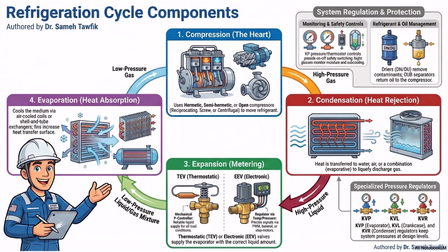Let's start with the KVP. This is the evaporator pressure regulator. It sits in the suction line after the evaporator. Okay, so after the chiller. Right. Its sole job is to prevent the evaporating pressure from dropping below a designated safety line. If the pressure in the evaporator drops too low, the temperature plummets.